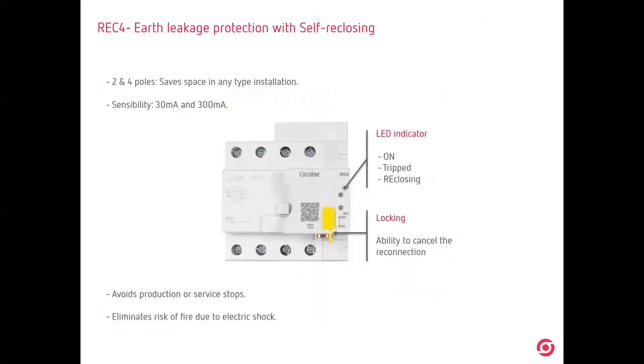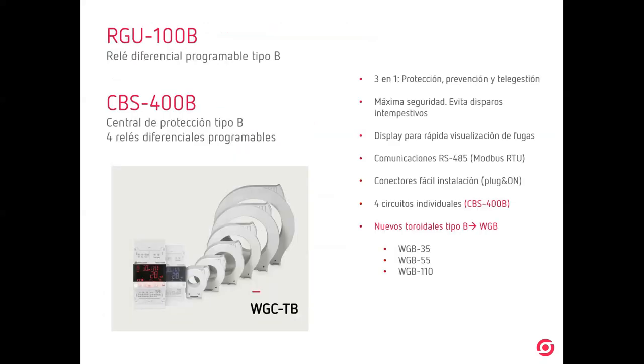And this is only for self-reclosing. This is earth leakage residual current protection with self-reclosing, 30 or 300 milliamps, two or four poles. When we have a fault, this will reconnect automatically, up to three times if the fault is permanent, for saving the installation and the people, avoiding production or service stops, or eliminating the risk of fire. So you have an installation on the mountain and you have a fault due to, for example, a lightning strike or something like that, and it is not permanent. The REC4 will reconnect the system without the need to send anyone there.